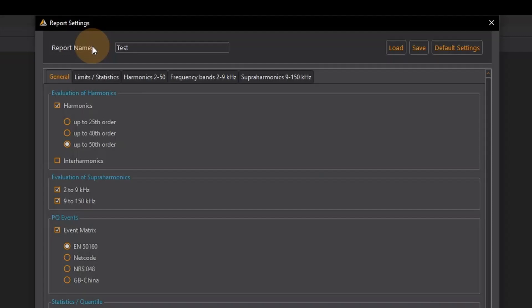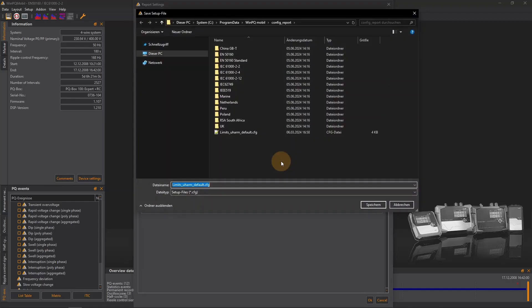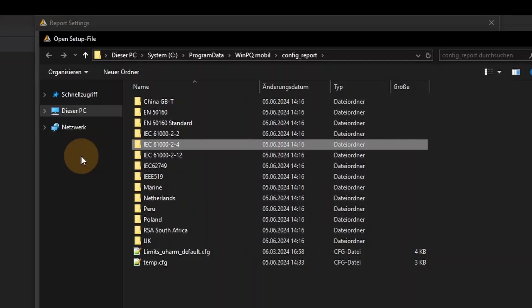As soon as I change a parameter in this window such as the name I have to save the current setting once as a file. I click on yes and save everything for this demonstration under the name temp. WinPQ Mobile offers a wide range of standards from all over the world for evaluating power quality. From EN 50160 which is widely used in Europe to the globally valid IEC 61000-2-4 for industrial networks and the IEEE 519. If I get confused with my settings I can load the default settings with just one click.